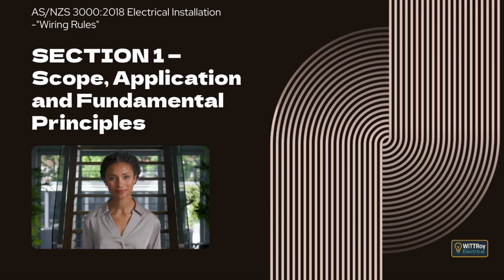Clause 1.8 Verification. Before an electrical installation, or any alteration or repair, is placed into service, it must be inspected and tested as far as practicable to confirm that it meets the requirements of ASNZS 3000. The inspection must avoid danger to people and avoid damage to property. If the work is an extension or alteration, it must also be checked to confirm that it does not reduce the safety of the existing installation. The correct connection of conductors to control and protective devices must be verified.